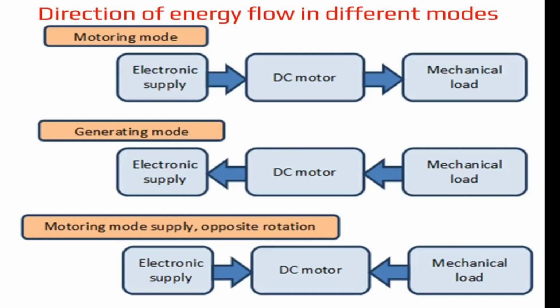Most servo drives are operated in all 4 quadrants, and the conversion is done in 2 steps. First, the main voltage is rectified, forming an internal DC circuit. Then, with the use of a DC chopper in case of a DC motor, or an inverter with changeable frequency in case of an AC motor, the given motor will be supplied.